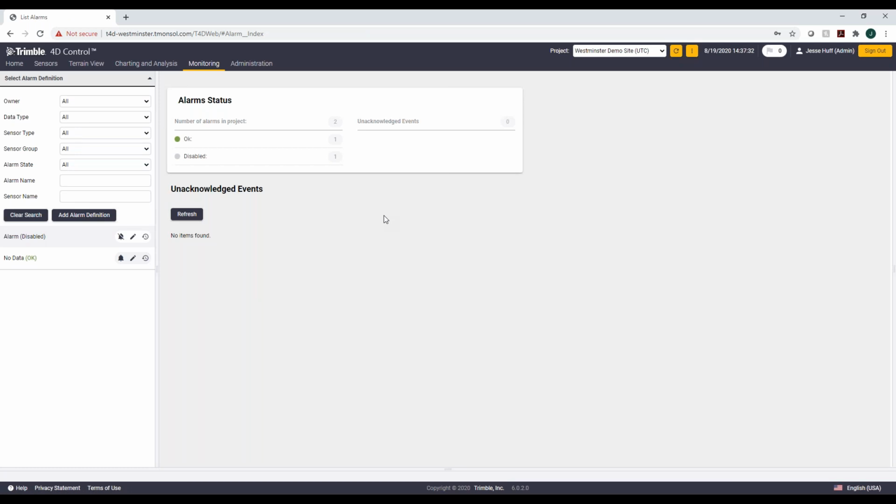And like Riley mentioned a little while ago at the start of the session, the whole idea behind generating alarms and alerts with a monitoring system is twofold. It's supposed to trigger human interaction for somebody to make a decision. Now, obviously, there are cases, certain thresholds that have to be met, where maybe you want to trigger alarms, alerts, send emails, maybe trigger flashing lights and beacons and things like that. All of that can be done through the alarming module here. But the whole idea is to trigger human response from this.